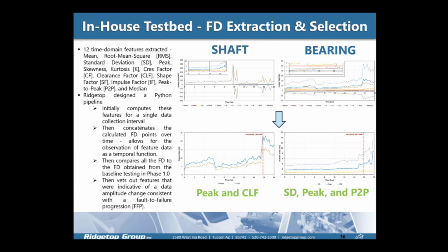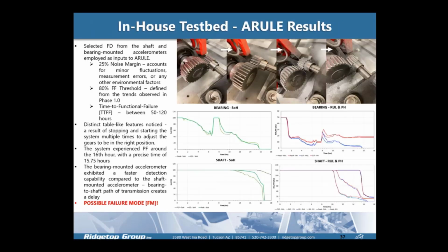Shown here on top is a chronological visual of the gear teeth. As you can see on the left here, they're very sharp, but over time, they got completely ground down. The interesting fact about this experiment is that the gears ground themselves to failure without any human notching on them. All this happened automatically, and we were able to observe this failure mode.